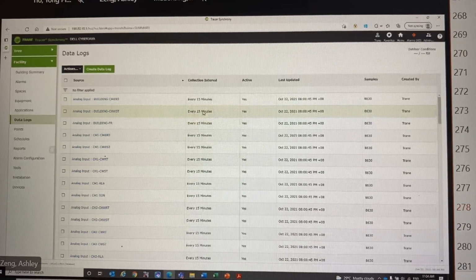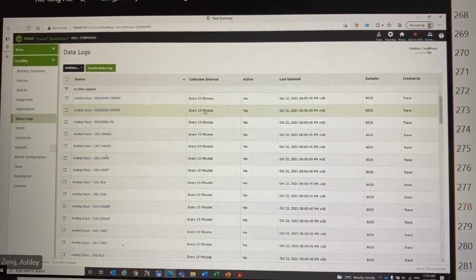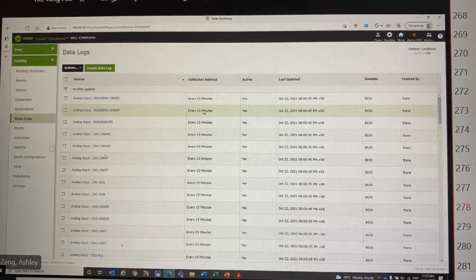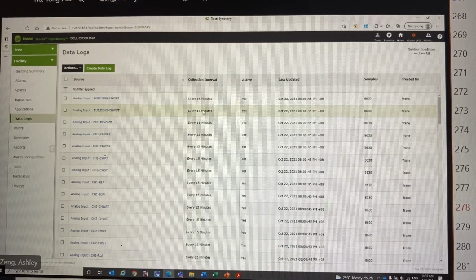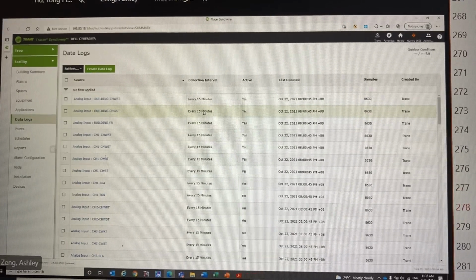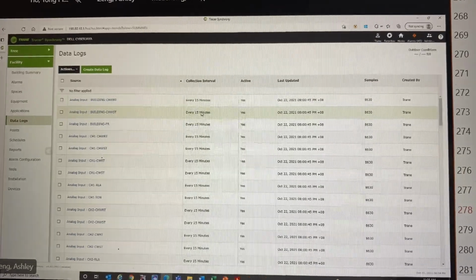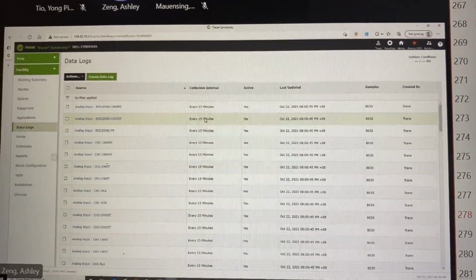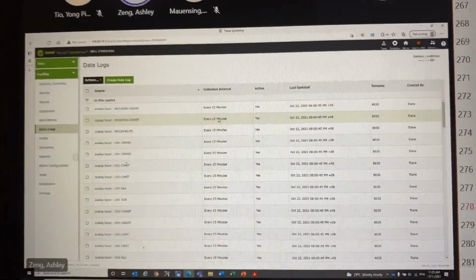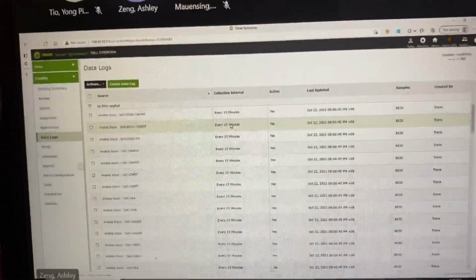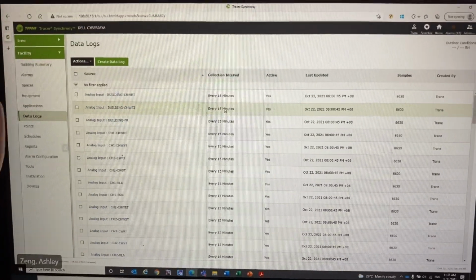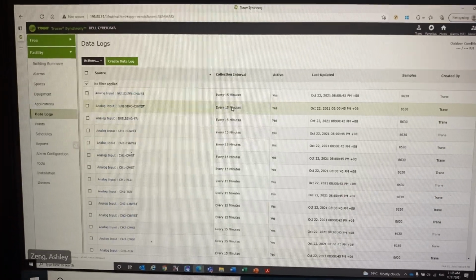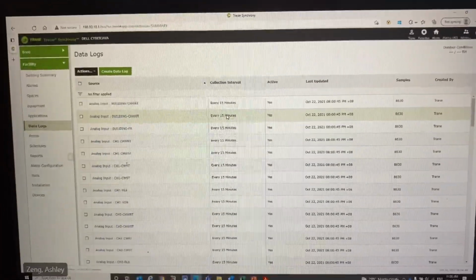But for air side, 15 minutes of data collection is more than sufficient because you do not experience a spike or sudden change so frequently. For equipment like FCU and AHU, 15 minutes is more than enough, so you can set it at 15 minutes. Unless the users have a requirement to do it at 10 minutes or whatever, then you set accordingly.